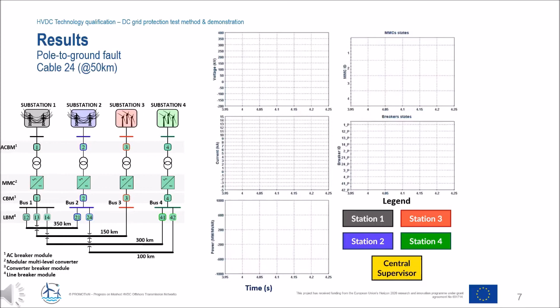This is an example of results we obtained for the CBS strategy. A fault is applied in the middle of cable 2-4. The graphs show a fault happening at 4 seconds, being cleared about 20 milliseconds after that, and the system being restored around 200 milliseconds after.